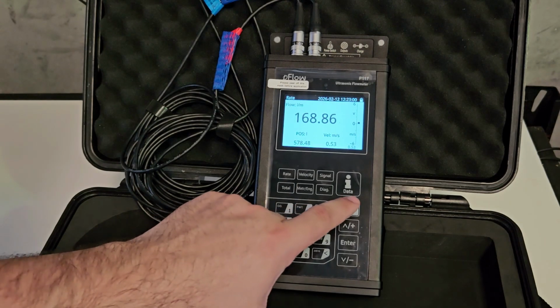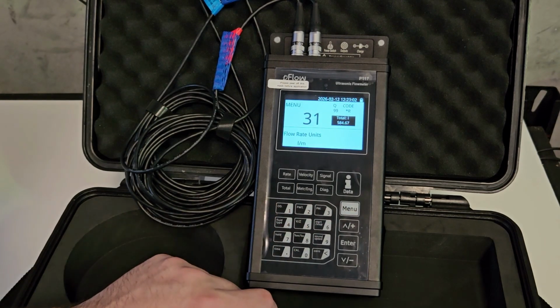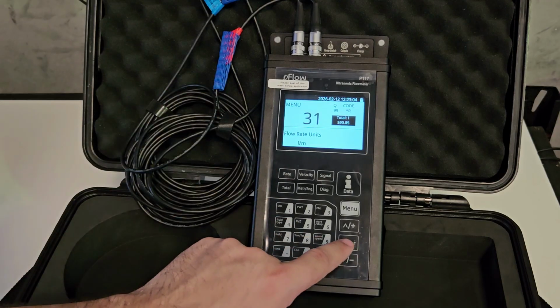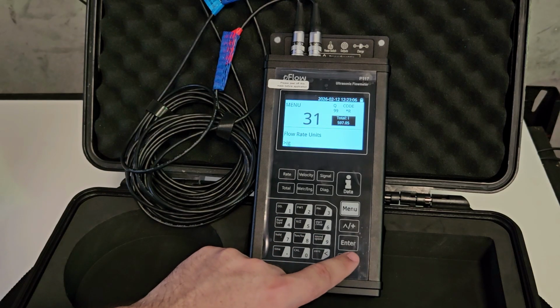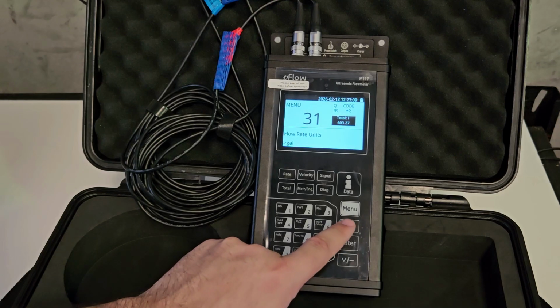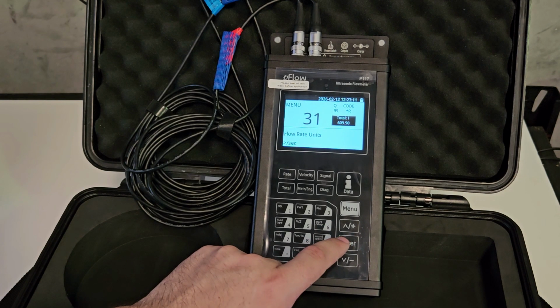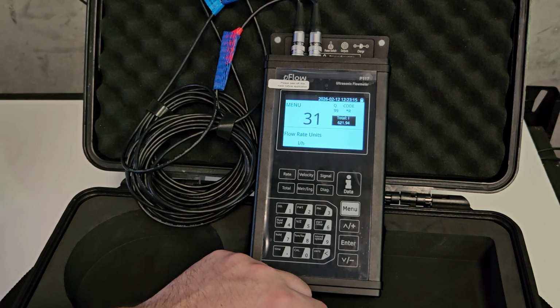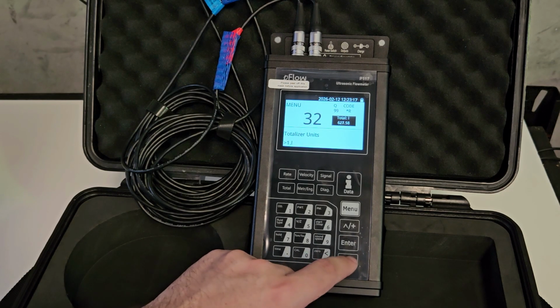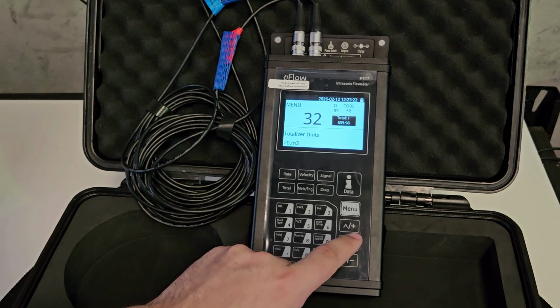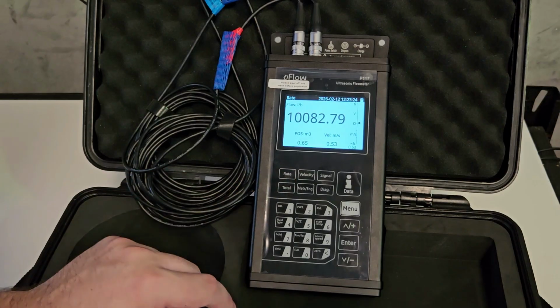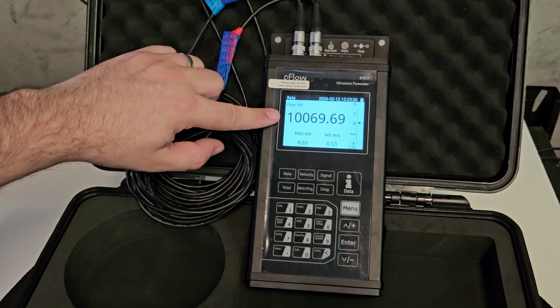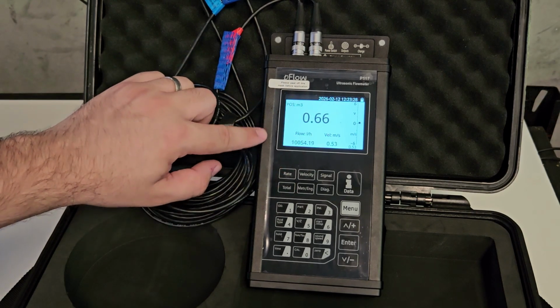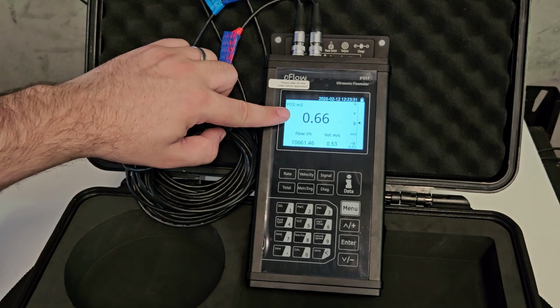If you want to change the flow units, they can be changed on menu 31. Press enter, scroll the list of units, then enter to select. You can then choose a time unit. So here I demonstrate setting it to liters per hour. Then the totalizer unit, if you want to change, it is on menu 32. Press enter, scroll the list of units, then enter to select. Now on the rate display my units have changed as it was set. Also on the total display, the unit has changed as it was set.